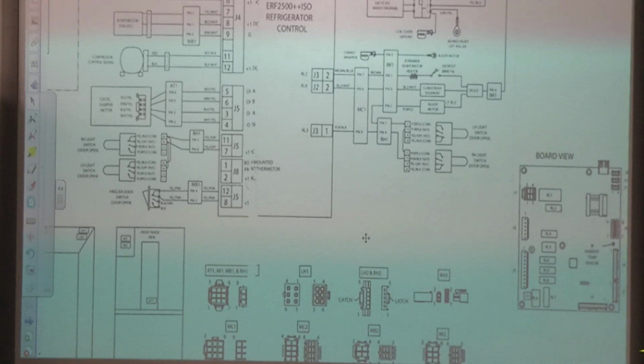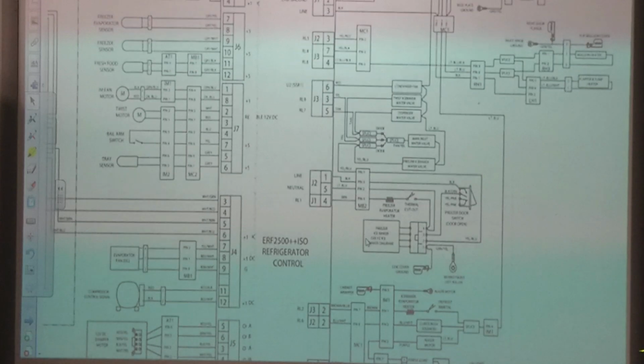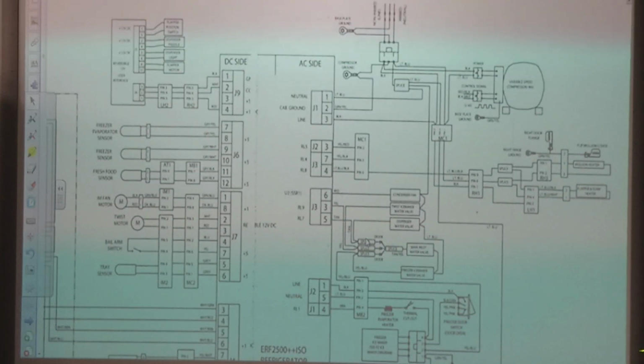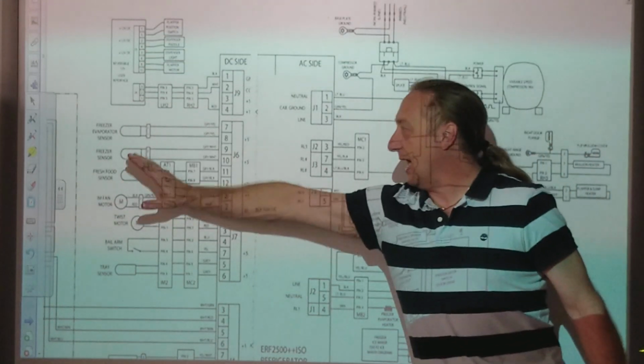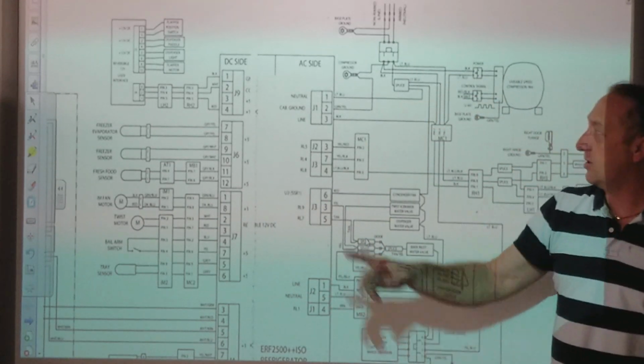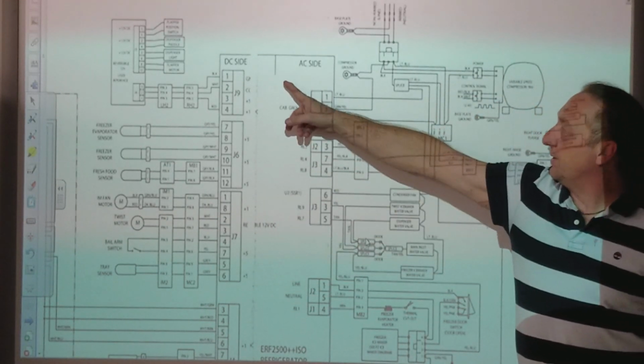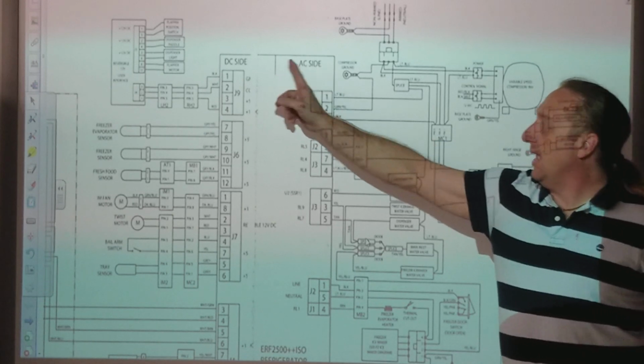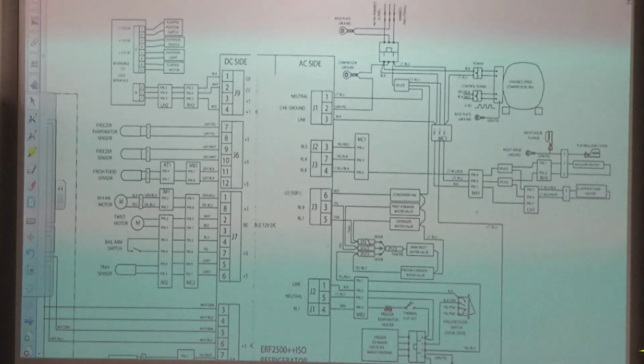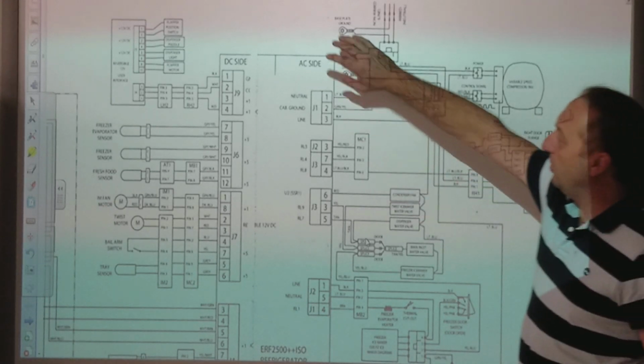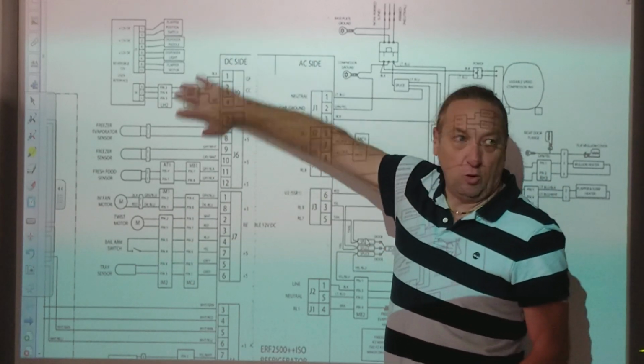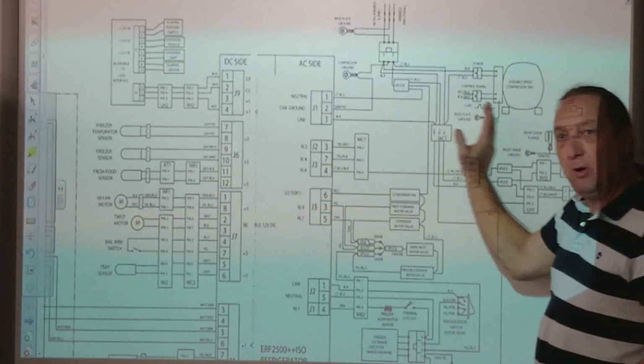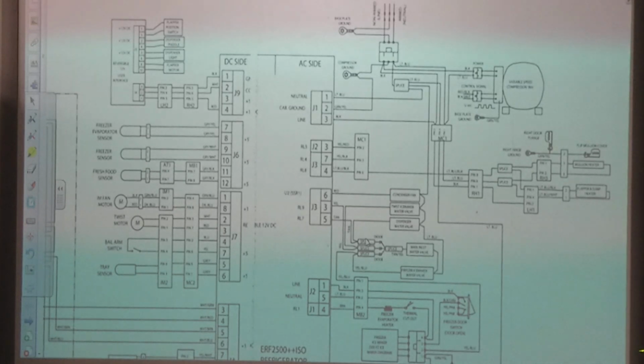Okay, let's go a little bit further down. Now this diagram was scanned in such high resolution I had to scan half of it and then the other half and put it together, so that's why you see a line here. But this line is factory, and it says AC and DC side. So part of this control board has AC voltage, alternating current, and the other half is DC, direct current. All the components over here are running off of DC volts, and we'll talk about that in a minute. All the components over here are AC volts.